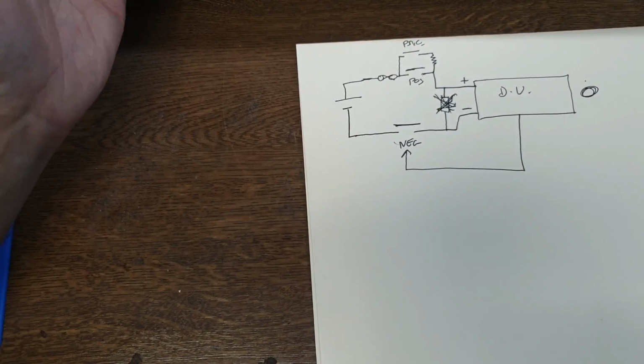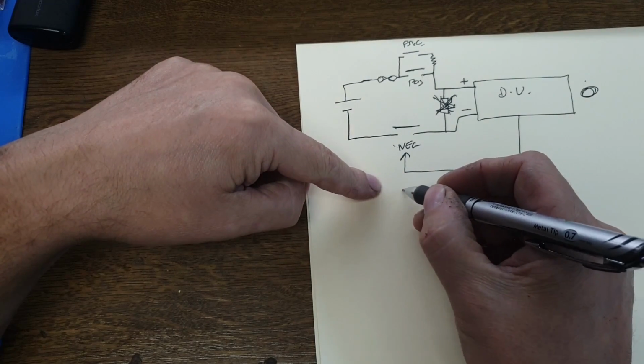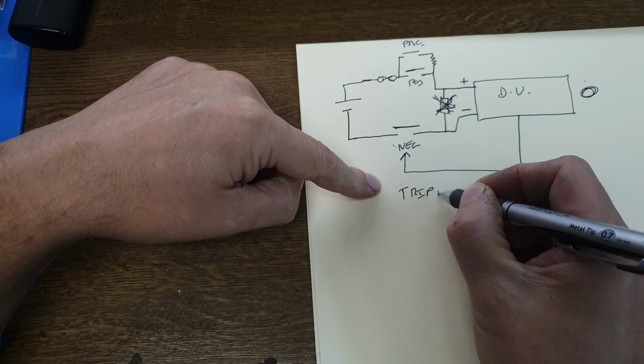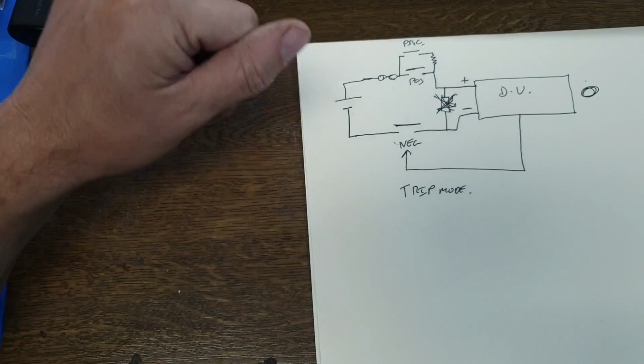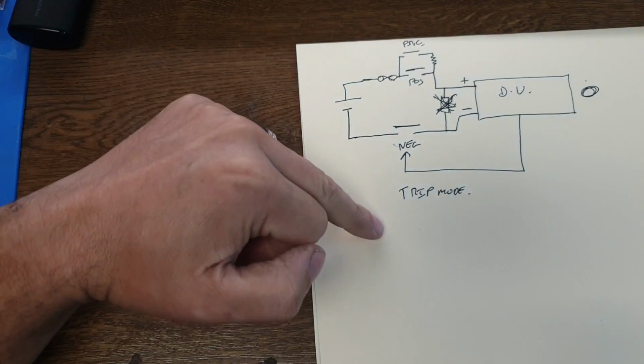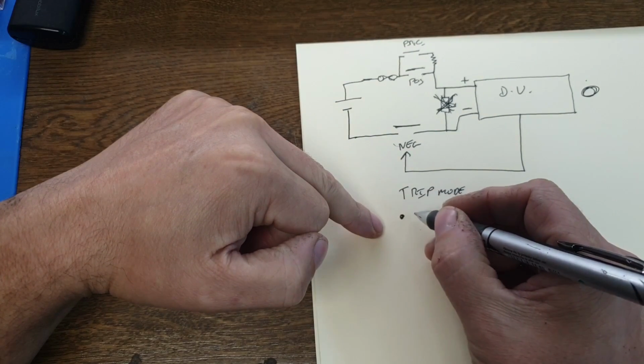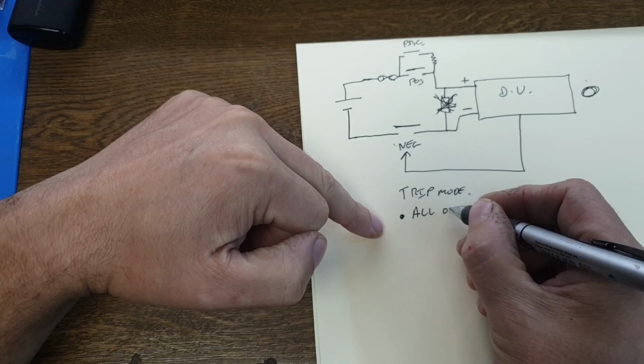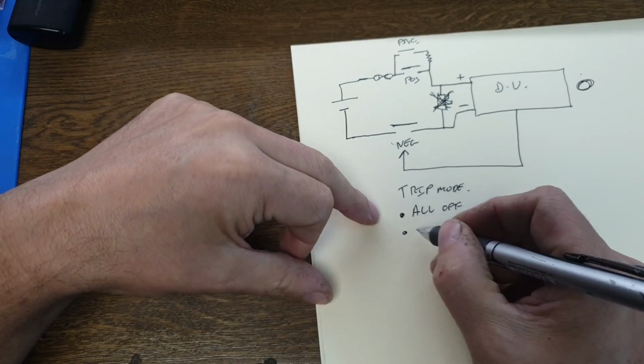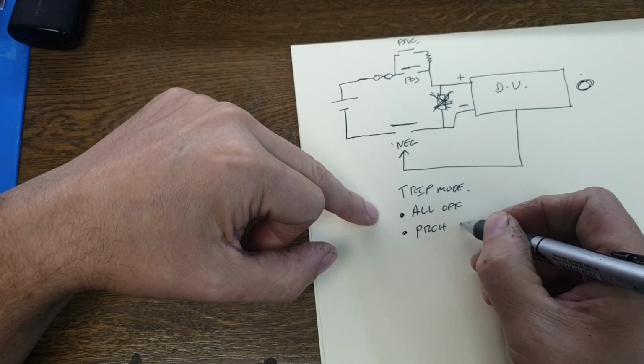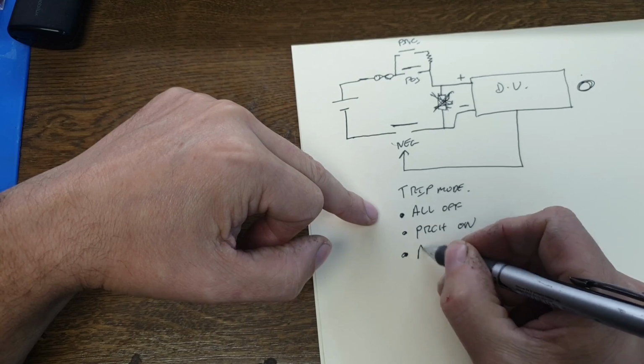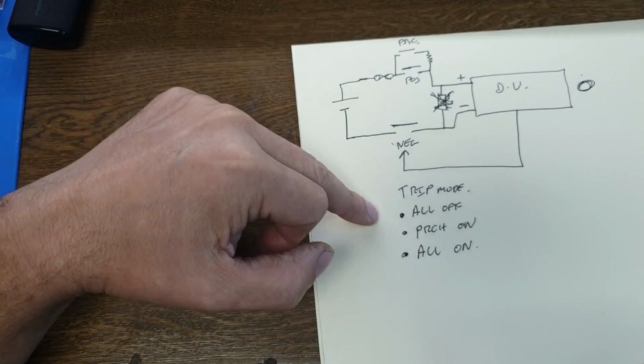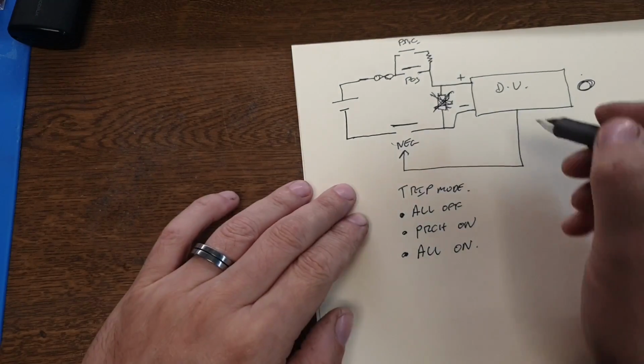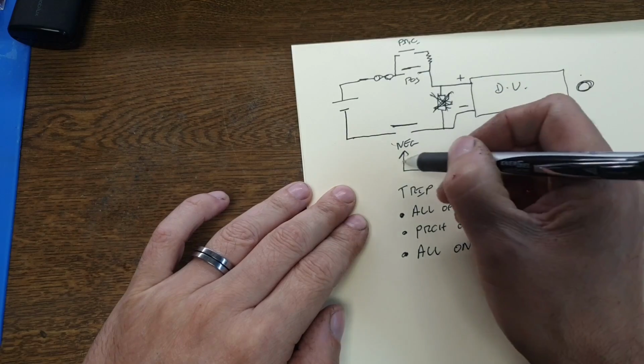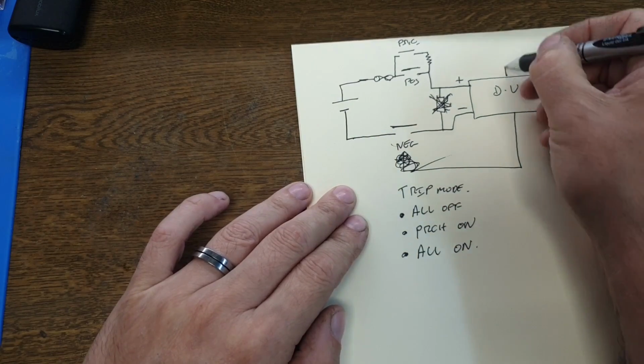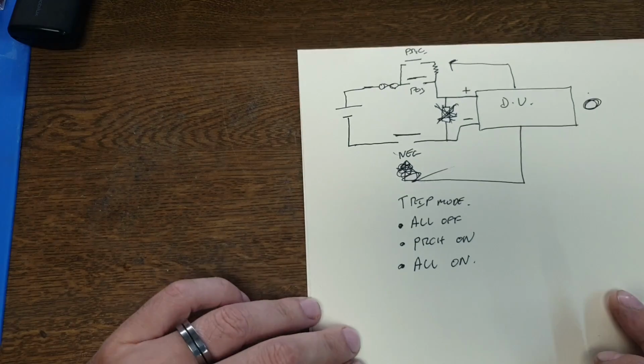Some people use it, some people don't. But there is a trip mode in the web interface parameter, and the choices are, from the top of my head, something like this: all off, pre-charge on, all on. I should point out the drive unit doesn't control the negative contactor, so that's a poor choice. It can control the pre-charge and the main contactor.